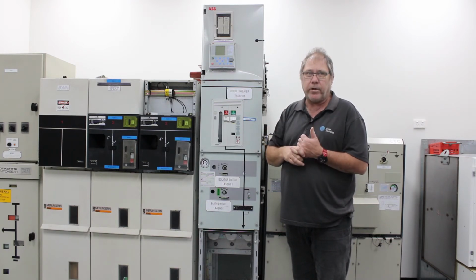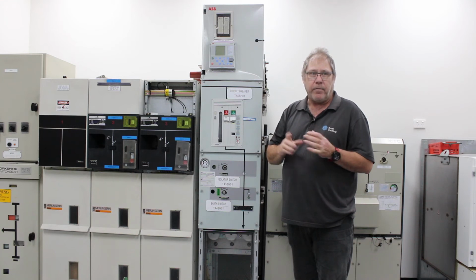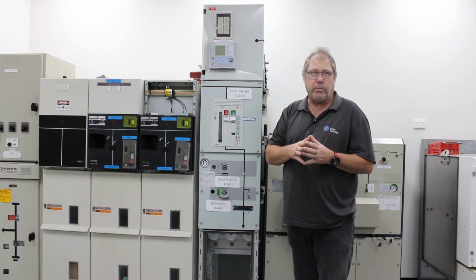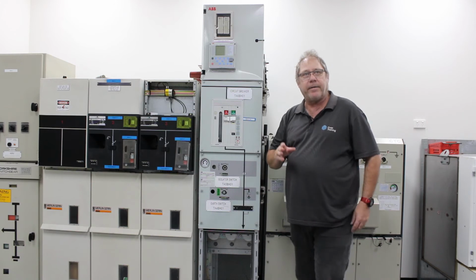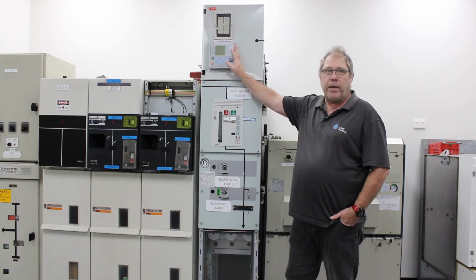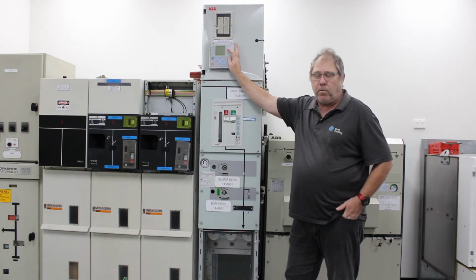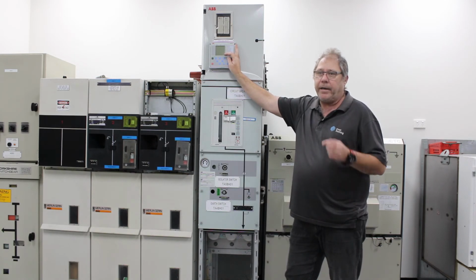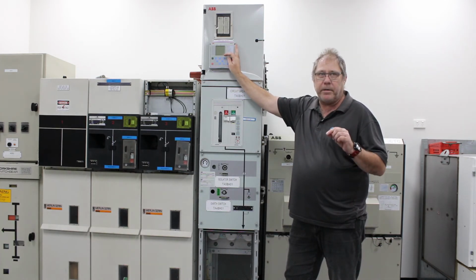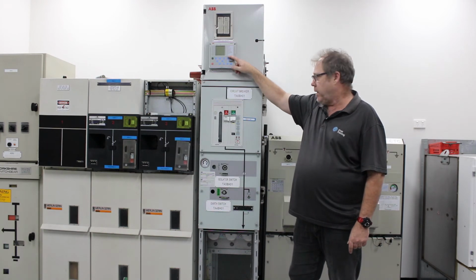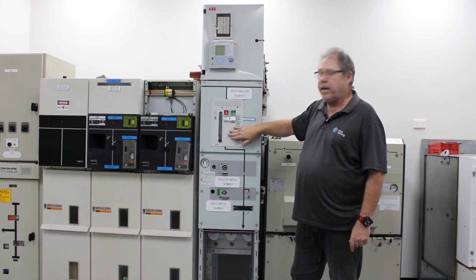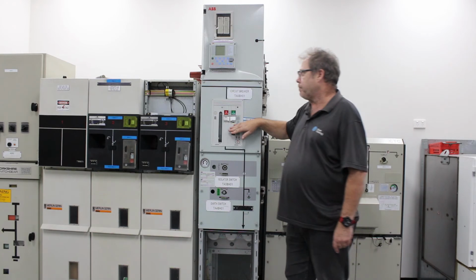If there is a short circuit or an earth fault, the current transformers downstream will pick that up, and again, that feedback goes through the protection relay, so the protection relay can detect there's a problem, and if it does not fit within parameters, this particular relay will then speak to the circuit breaker and tell the circuit breaker to trip.